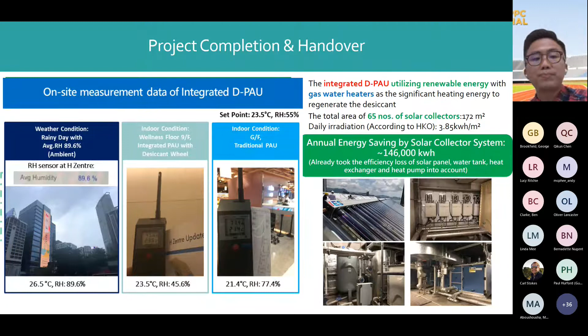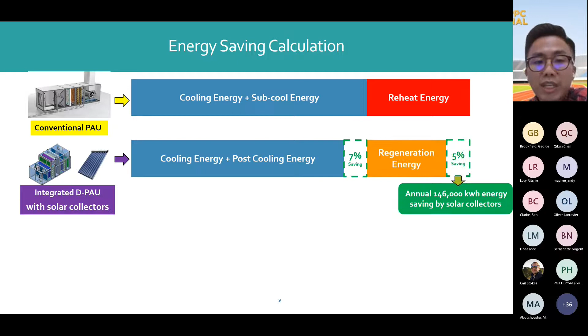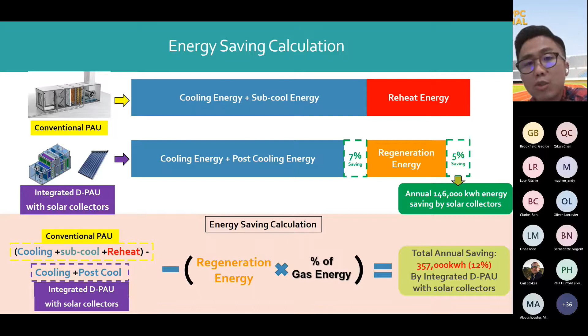Compared to the conventional air conditioning dehumidification method, the gas dehumidification system could achieve 7% cooling energy saving. The solar energy utilization brings another 5% energy saving for the desiccant wheel regeneration, so the total energy saving is 12%, and the annual energy saving is around 357,000 kWh, according to the operation hours. The energy saving calculation is based on the psychrometric chart and also the actual gas consumption for the desiccant wheel regeneration process. To conclude, the gas dehumidification has accomplished different environmental achievements.